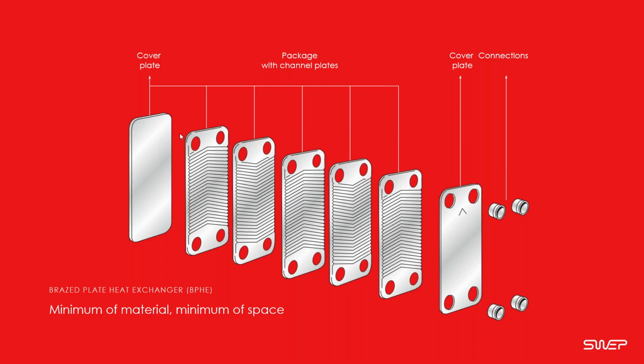Once the heat exchanger has been assembled according to the design specification, number of plates, plate pattern, connections, and so on, it then goes into the furnace and is brazed with usually a copper brazed material, and it's then tested. Every single unit is pressure tested to design pressure and beyond, and then they're labeled and packed and sent out. So it's quite a rigorous production process that we go through for each and every single heat exchanger.